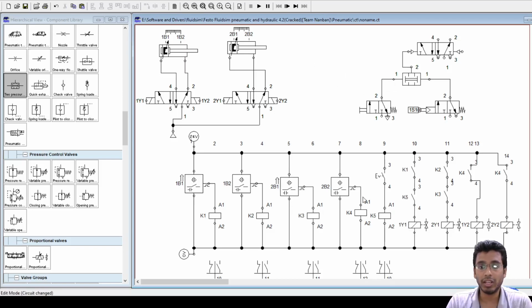So this is where your actual difference comes from if you compare electro-pneumatic and pneumatic alone. In pneumatic, the pneumatic pressure itself is a signal, right? That is why at the end, when you do all the processing of all the pneumatic signals, finally how do you extend the cylinder? By your pilot operated valve, right? So finally you have your pilot operated valve here, which is used to shift this spool, and then your cylinder extends, right?